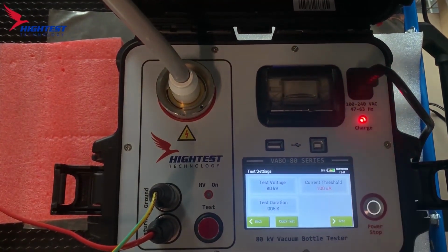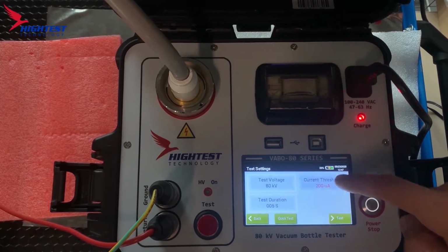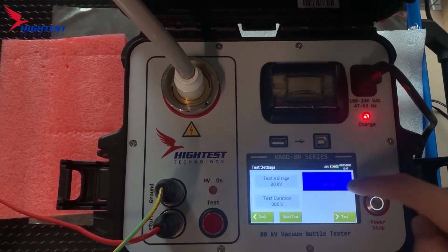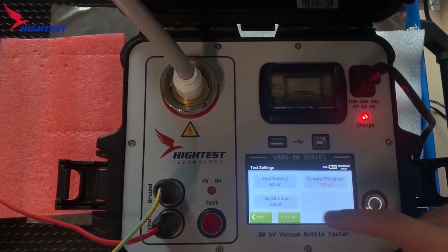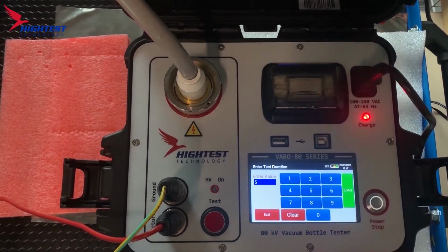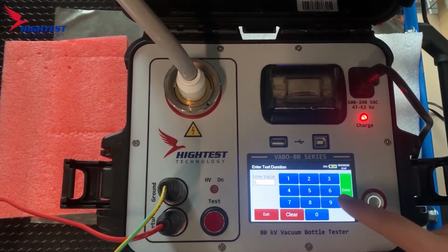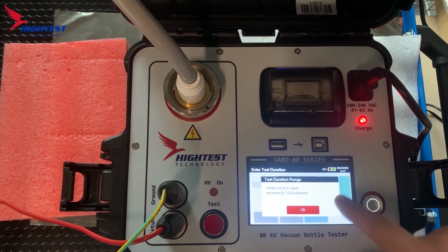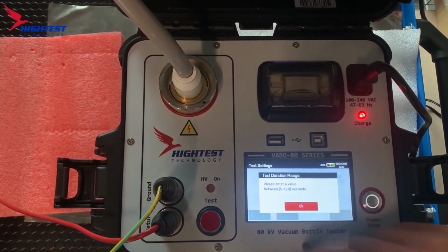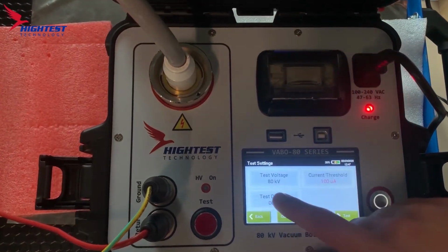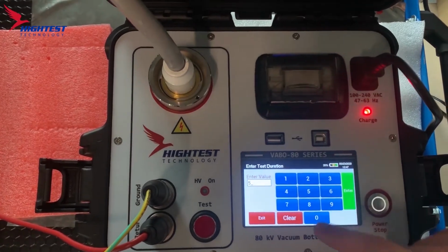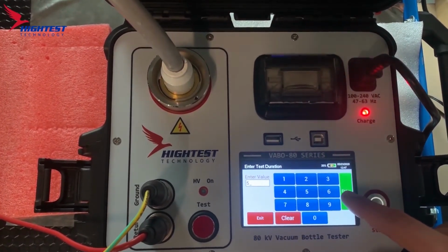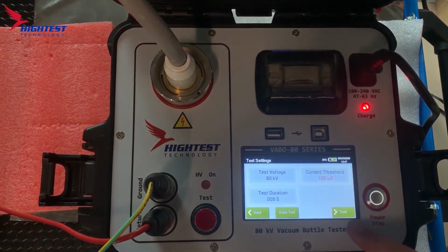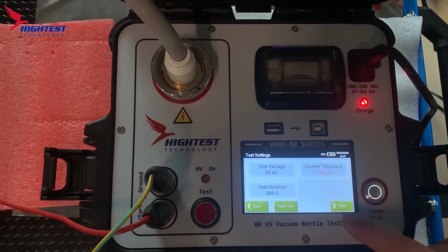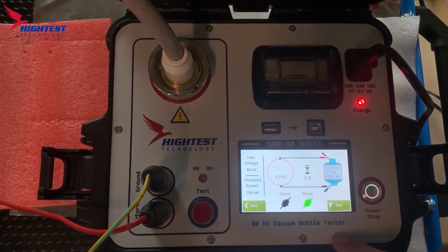We have our current threshold that we can change from 100, 200, or 300 microamps. And then we have our test duration between 5 seconds and 120 seconds. For the purposes of this test, we will be conducting it for 5 seconds. Once you are done changing your options, please select test.